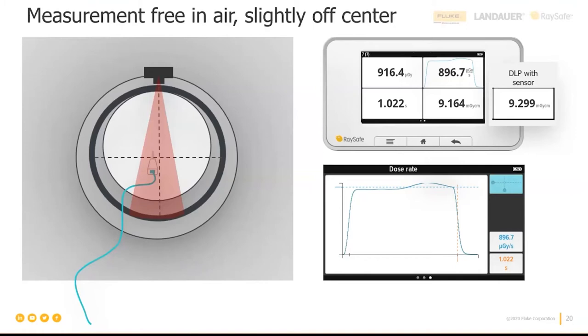So Anders, just a question about this. When you do constancy tests, this means that when you compare your measurements from that of, let's say, the previous year, and you see that the numbers differ, then you can check in the waveform, right? And see if it's the positioning of the sensor that makes a difference, or if it's the machine, is that correct? Yeah.